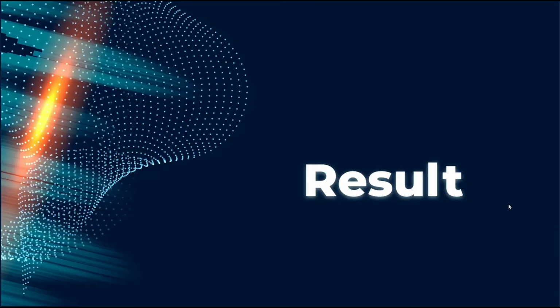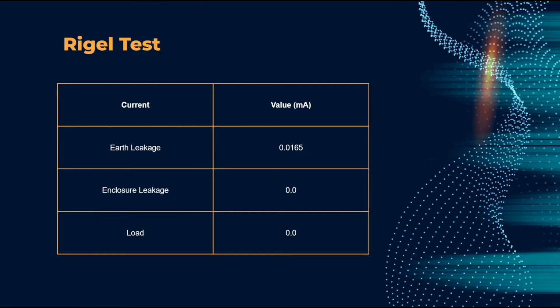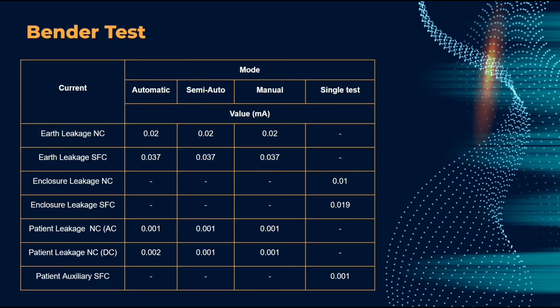Hello, my name is Razil Biazian. I'll be explaining the results for our project. The first test is the Rigel test. On this test, we got 3 different values of current. First one is earth leakage current, followed by enclosure leakage current and load current. The second test that we have done is the Bender test. This test has provided us with the most values of current. We have done this test using 4 different modes: automatic, semi-auto, manual, and single test. This is because some of the values can only be found using the single test.